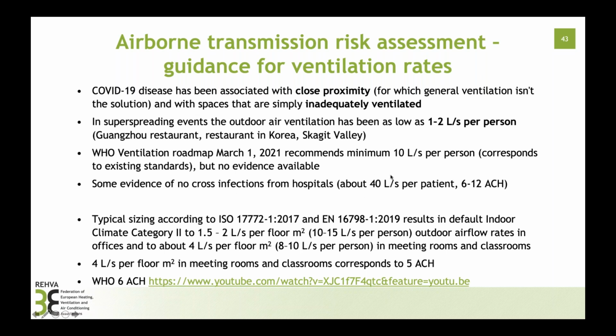Some evidence exists from hospitals, where we operate with 40 liters per second, so 6-12 air changes per hour. But if we do sizing according to existing standards, ISO or European standard, for classrooms or meeting rooms in common buildings today, 4 liters per second per floor square meter will end up with 5 air changes per hour. So there are rooms in common buildings where we can expect very high ventilation rates, which are actually quite close to hospital ventilation, also in common public buildings.